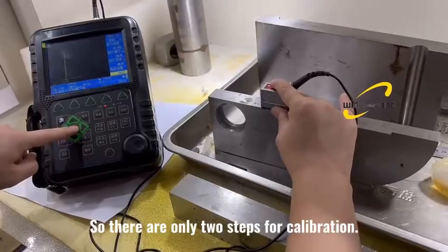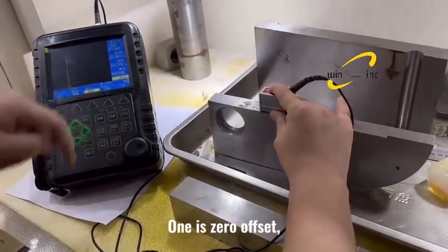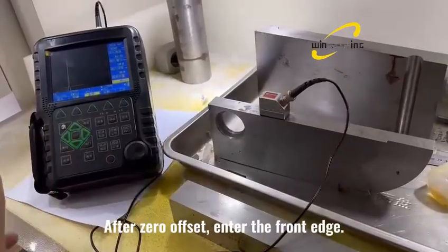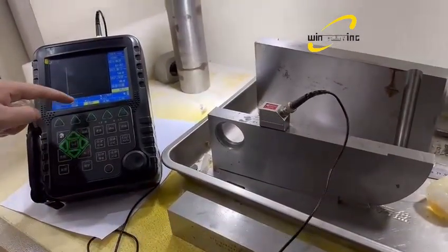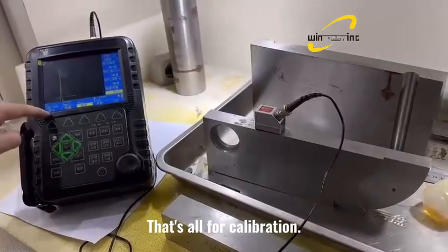So there are only 2 steps for calibration. One is zero offset. After zero offset, enter the front edge. The other is to calibrate the angle. That's all for calibration. We have finished.